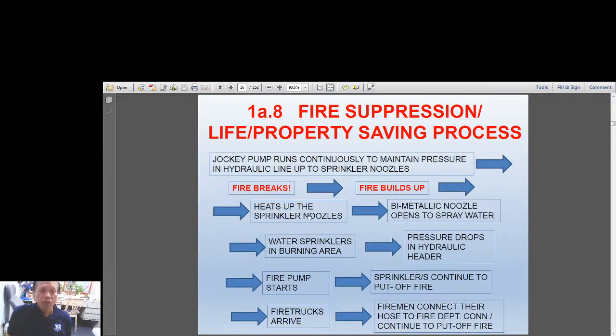The sprinkler will then operate because it works like a bimetallic spray nozzle. So it heats up the sprinkler nozzle. The nozzle will start to sprinkle water, and immediately when the water sprinkles, the pressure of water inside the hydraulic system, the sprinkler system, will drop rapidly. It will drop rapidly, and the sensor at the header near the fire pump will actuate the fire pump to start. So automatically the fire pump will start, and therefore the fire pump will deliver the fire water. At the initial point, the sprinkler nearest to the fire will just be the initiator.